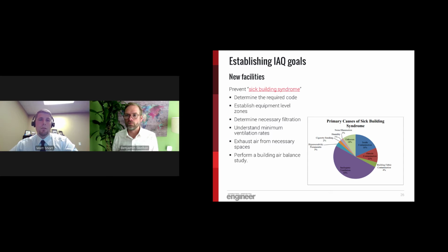Next, work to establish equipment level zones, determine how the building should be conditioned. From there, determine the code required level of filtration for each of these zones. Taking the facility baseline, we can then understand the minimum ventilation rates for each zone based on the space requirements within each zone. Next, it's important to determine which spaces require air to be exhausted from the building and how they interact with any adjacent spaces.